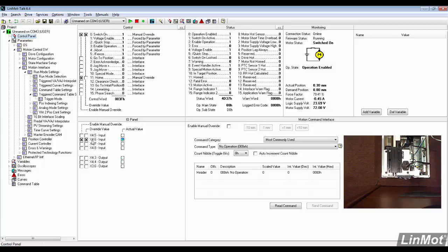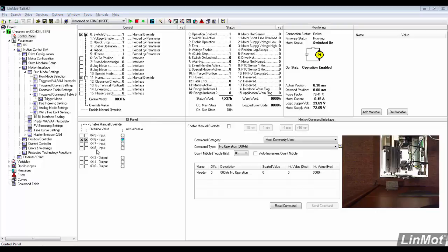When there's nothing to press, the motor current is too low, and X4.3 shows that there is an error. When there is something to press against, but the motor travels less than 51 millimeters, an error occurs.